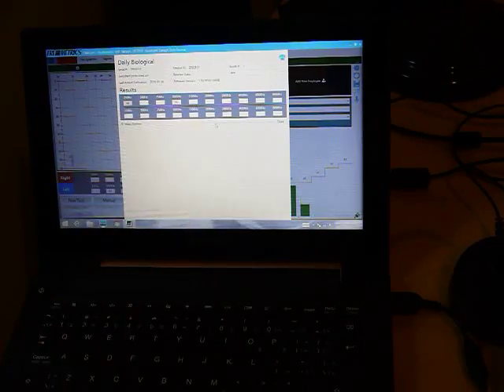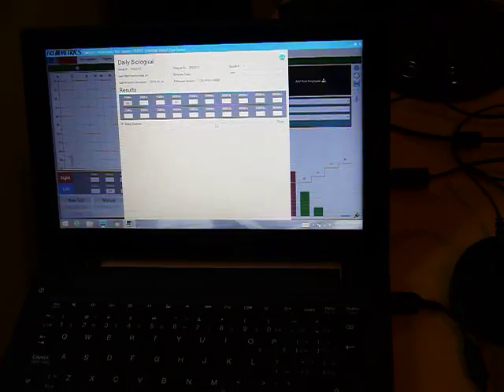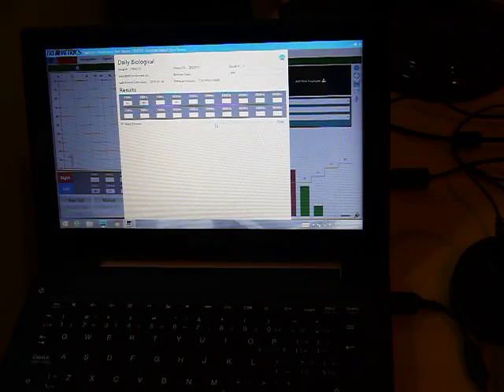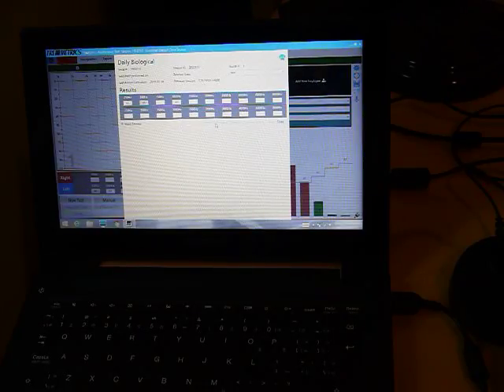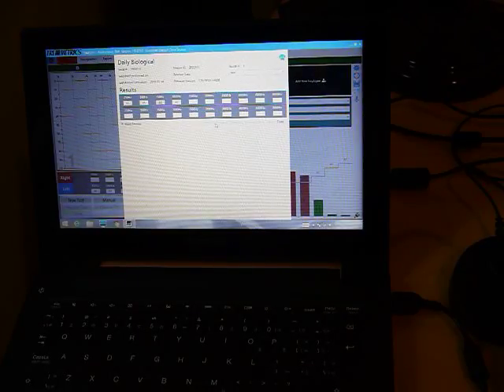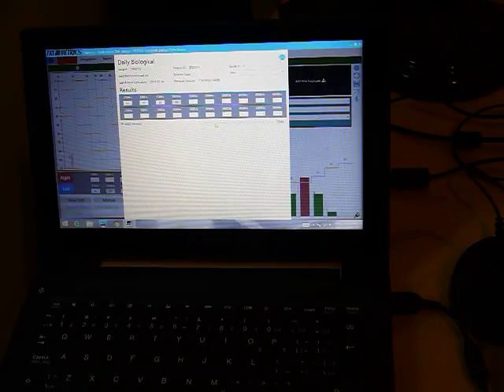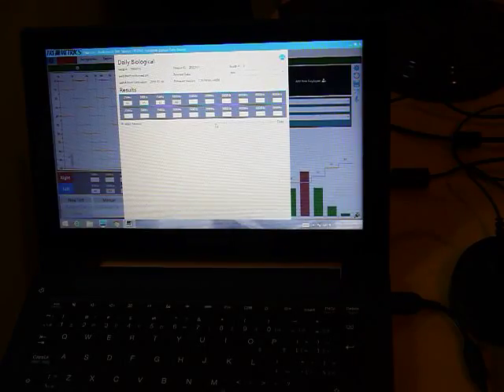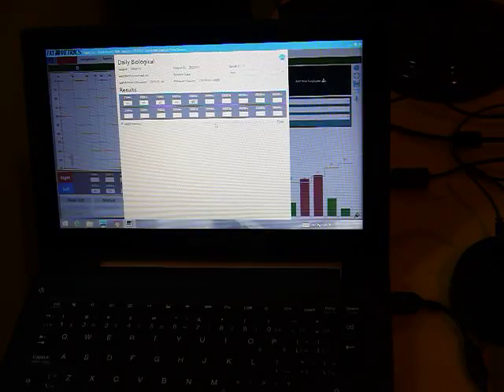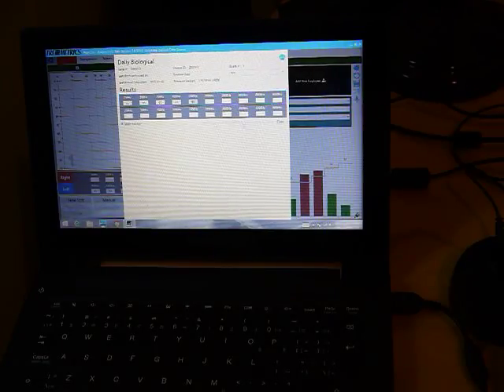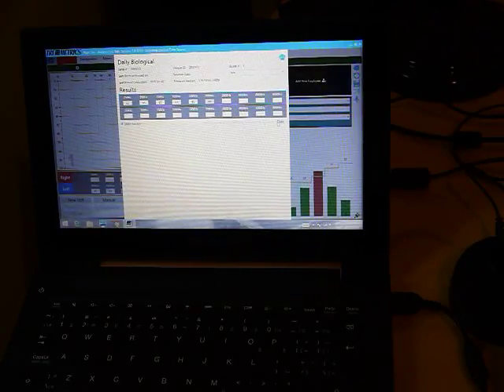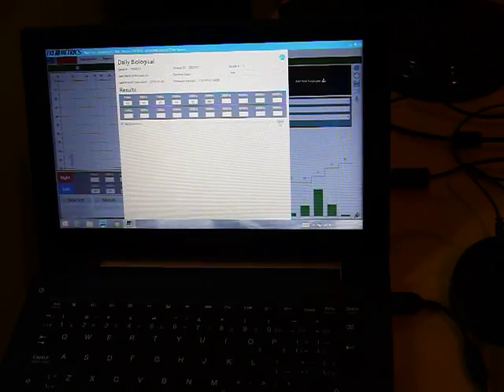It's starting to test and make sure that the headphones are good, that everything's working, that there weren't any issues. We had customers have issues with the wires breaking and things like that on older audiometers. It's just a good way to test before the start of each day. I'm going to stop that right now.